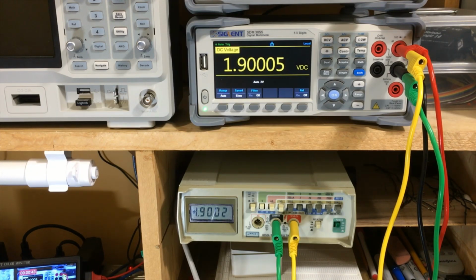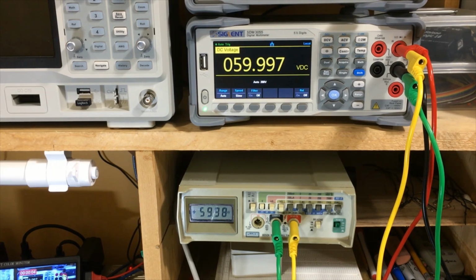Now I also want to check the 200 volt range, but Fluke recommend 190 volts. I don't have 190 volts, so what I'm going to do is set up my power supply over here to run about 60 volts, and we'll try to get it up to 60 volts, and then we compare the Siglent to the Fluke. Okay, we got it on the 200 volt range here. We got 59.997 volts going in, and we're reading 59.98. So a little bit of fluctuation here and there, but the readings are generally within a couple of counts. So yeah, this meter is perfectly usable.